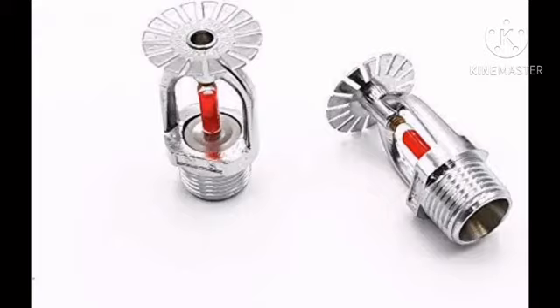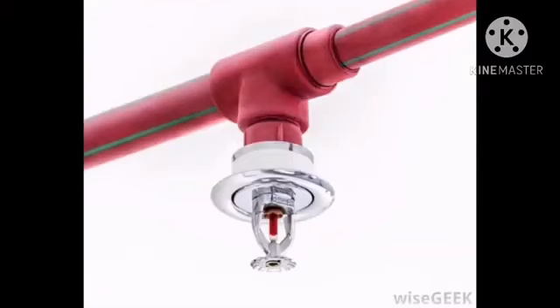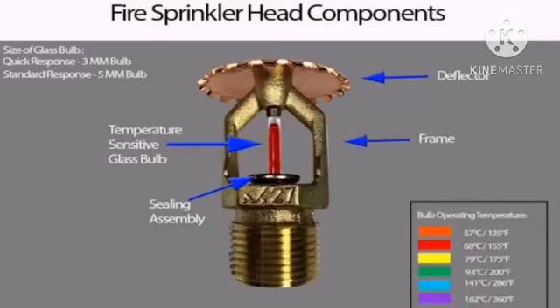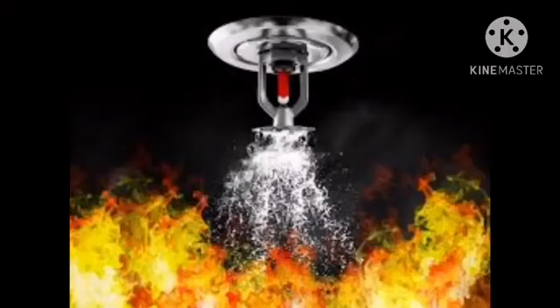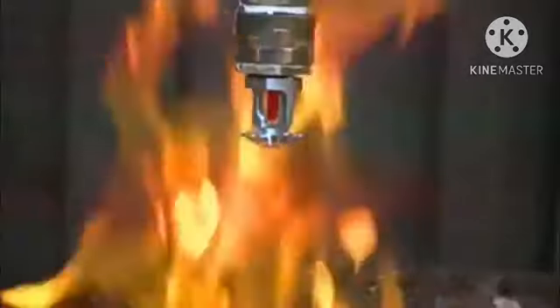One of the most important components of a fire protection system is the automatic fire sprinklers. In general, a sprinkler is activated by the heat put off by the fire once it reaches a certain temperature at the ceiling around that particular head. A common misconception is that every sprinkler head in a system will go off at once after the first sprinkler has activated. While systems that behave somewhat like this exist, deluge-type systems, it is pretty uncommon and used in special situations like certain types of aircraft hangars. In most cases, the fire sprinklers that activate only do so around and over the fire.